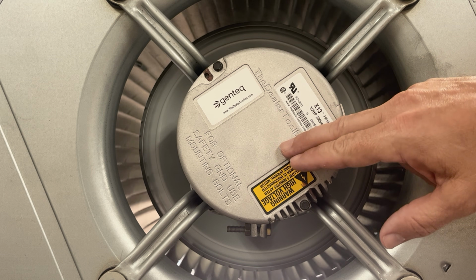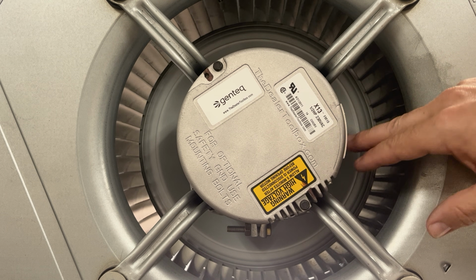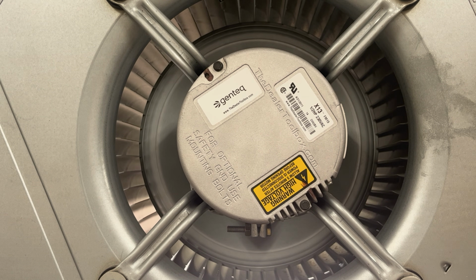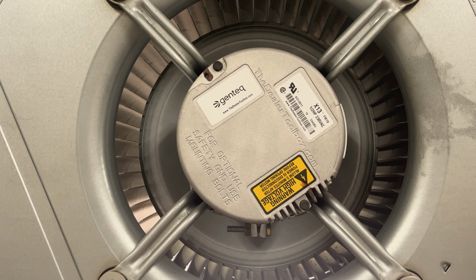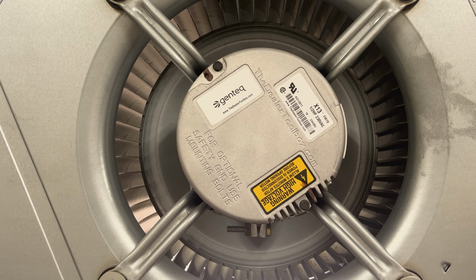But that's the only way to be able to test those windings, because there is a relay in here that's in the normally open position. It is breaking a leg of power. So yeah, even though your motor has 230 volts on it, the motor actually doesn't have 230 volts on it, because if it did, it would run. It needs 24 volts to close the relay inside the back of the module, so it can run. That's why we don't run with relays or blower control boards anymore, because they're all built in here.